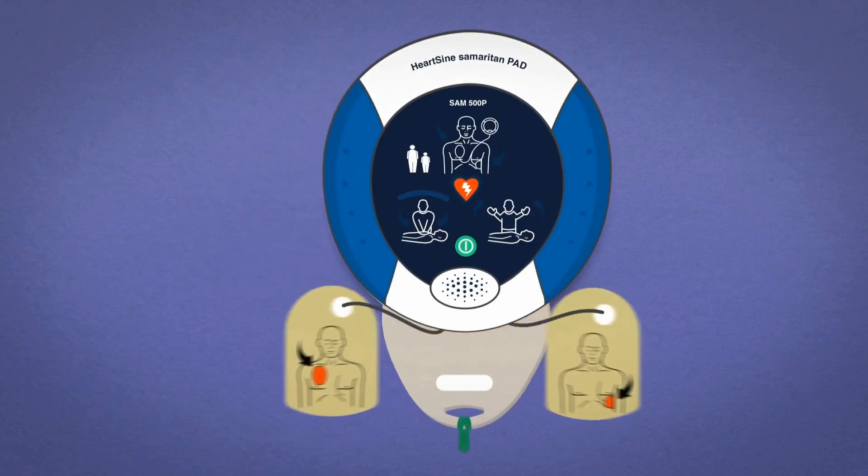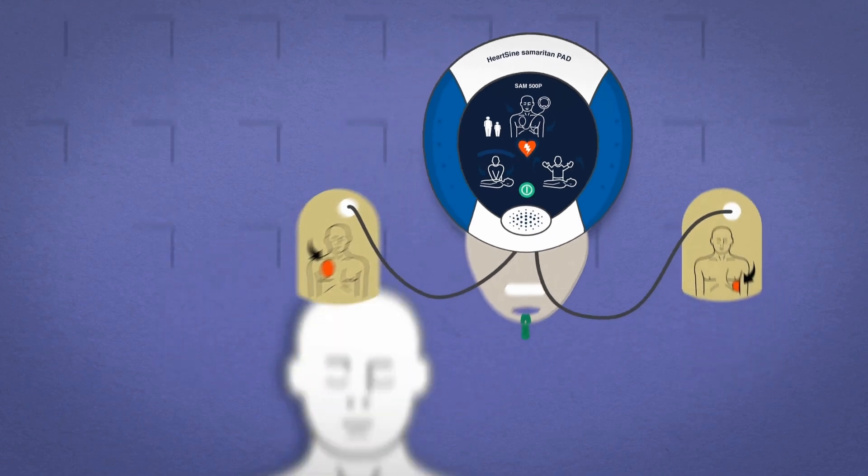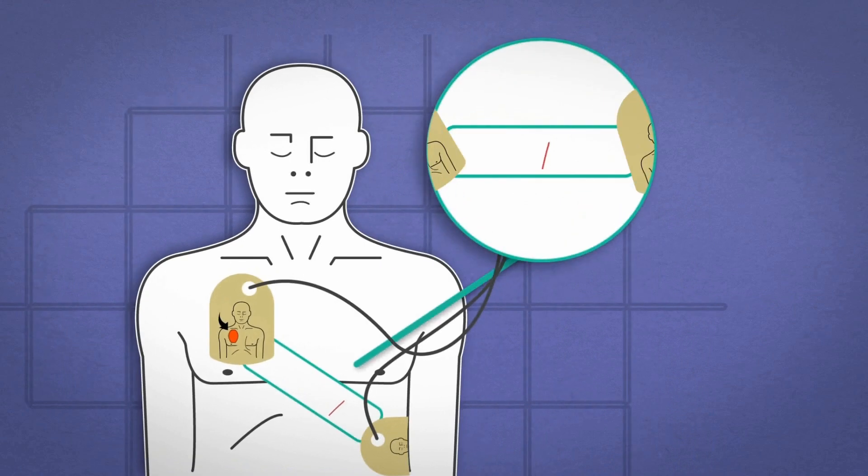With its revolutionary technology, HeartSine's patented CPR Advisor uses only the defibrillator electrodes to detect changes in patient impedance, rather than accelerometers or pucks commonly used in other AED solutions. The changes in impedance are related to the rate and force of compressions and correlate to a number of vital signs.